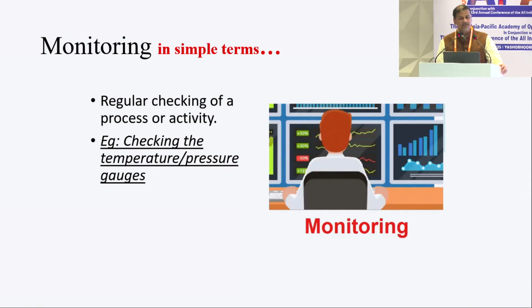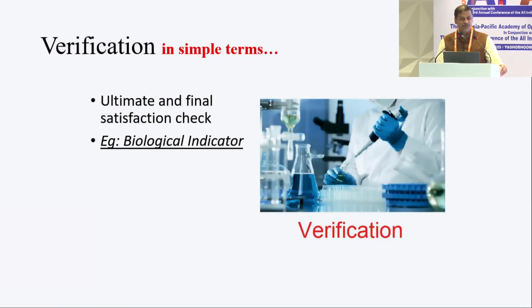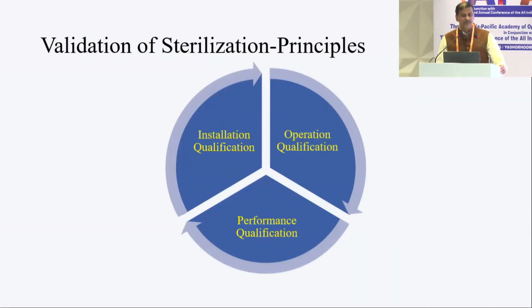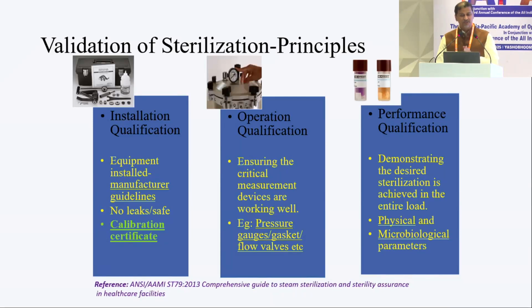Monitoring means a physical checking of all the parameters of temperature and pressure, and verification is also very important, and the most important part of verification is the biological indicator. So validation, monitoring and verification are an important part of a sterilization process, which could keep you away from medico-legal cases in case there's a sterilization failure and the patient ends up with endophthalmitis. Validation consists of three parts: installation qualification, which is supplied to you by the manufacturer, operation qualification and performance qualification. So the three parameters.